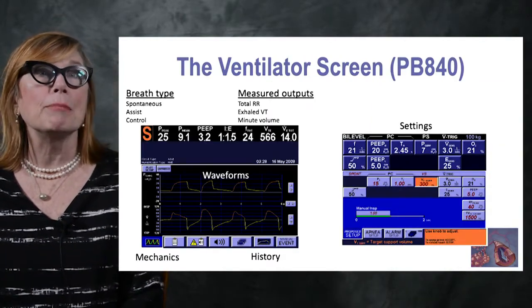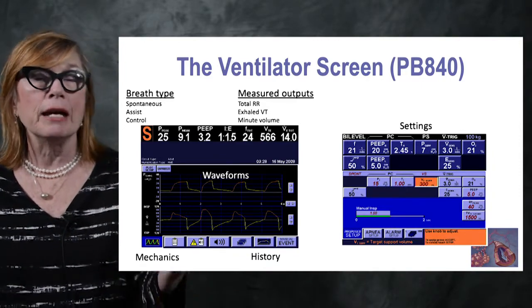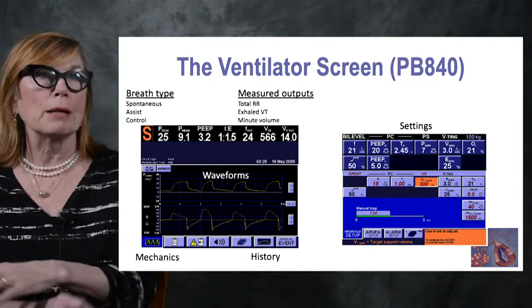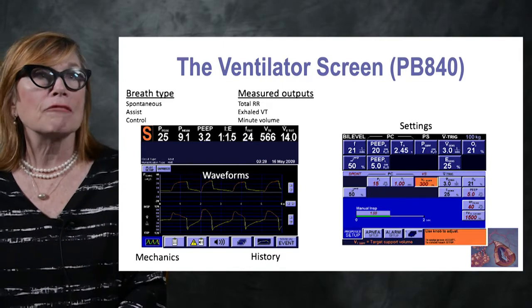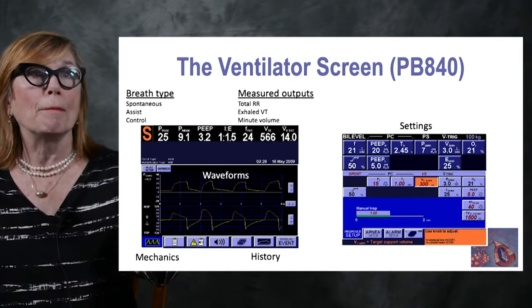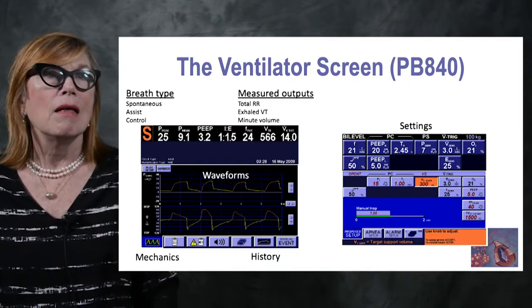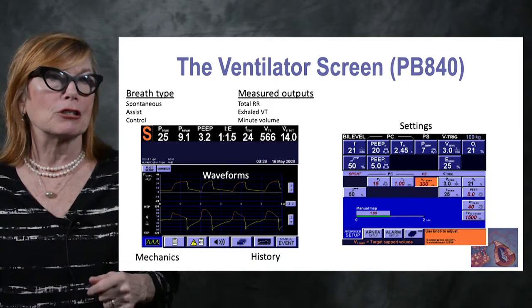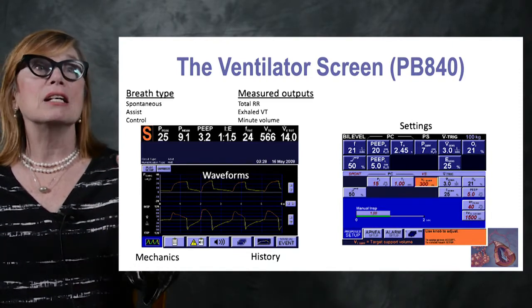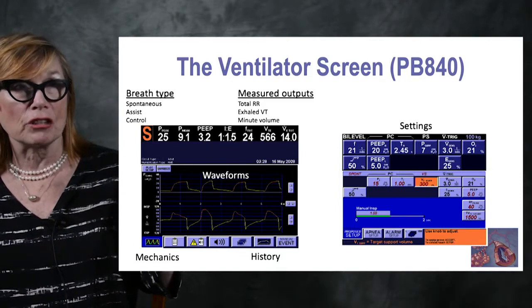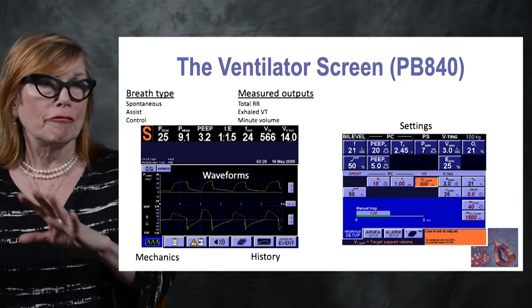Looking at the screen of the Puritan Bennett 840 — the predominant ventilator we use at Grady Hospital — in the upper left you see a big 'S' when the patient is taking a spontaneous breath, a big 'A' if the breath is spontaneous but then assisted by the ventilator, or a big 'C' when it's a complete ventilator breath. So we have three types of breath: total spontaneous, assisted, and controlled.